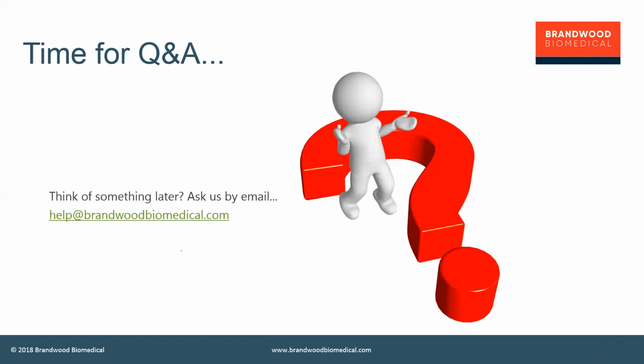Now, you do mention that you have a very new technology. It may be worth considering if your device is innovative and meets an unmet need, something that addresses the clinical need in a new way, whether you would be eligible for TGA's innovative device pathway. So TGA has developed an innovative device pathway, like many regulators have done. It's a relatively straightforward designation process.